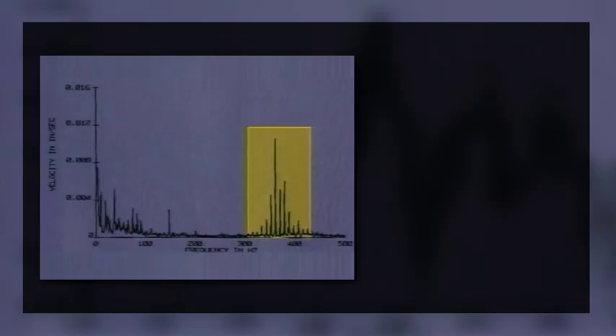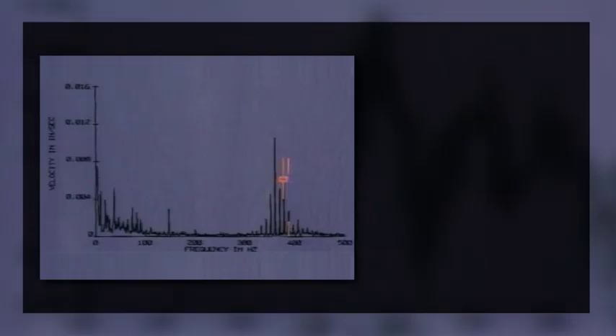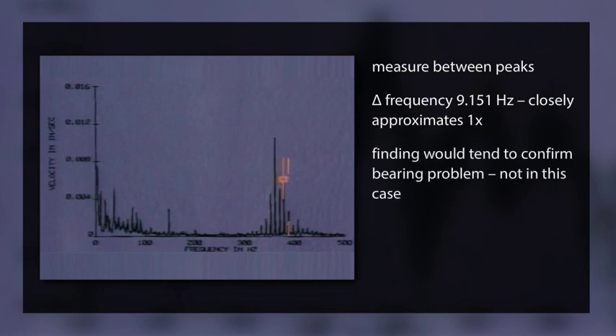So let's look at the family of peaks between 300 and 400 hertz. The pattern looks similar to a gear mesh frequency, but there are no gears in this pump. So what might this be? Well, sometimes you get lucky, and you catch a bearing defect in its infancy before the fault frequencies we're used to seeing can form. If you find a family of regularly spaced peaks at a relatively high frequency, measure the space between the peaks. In this case, we find a delta frequency of 9.151 hertz, which very closely approximates the one-times. Normally, this finding would tend to confirm a bearing problem, but perhaps not in this case.